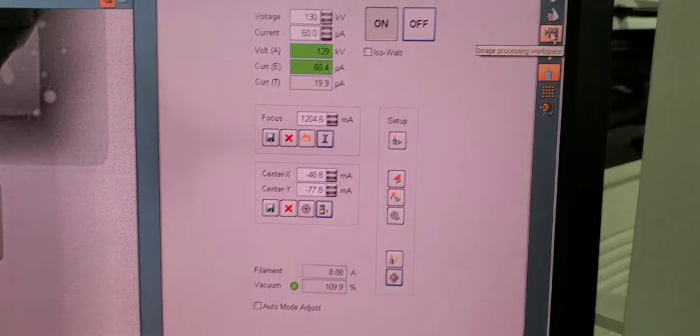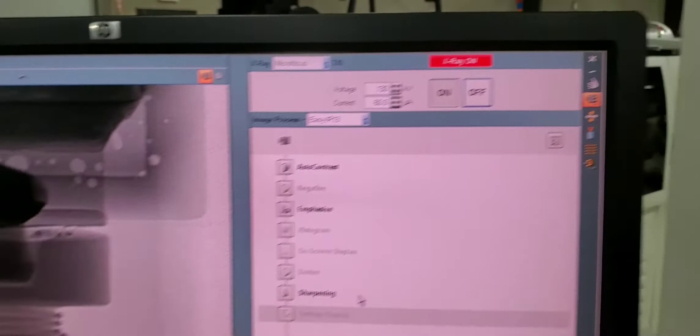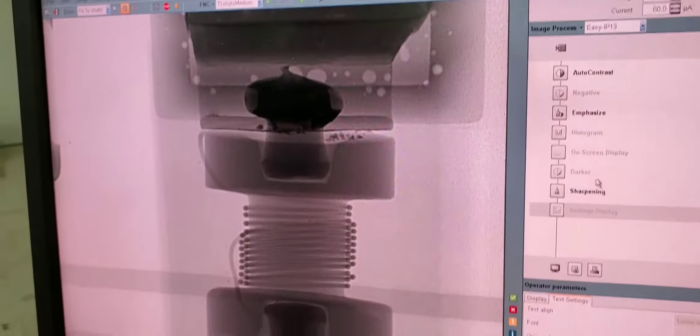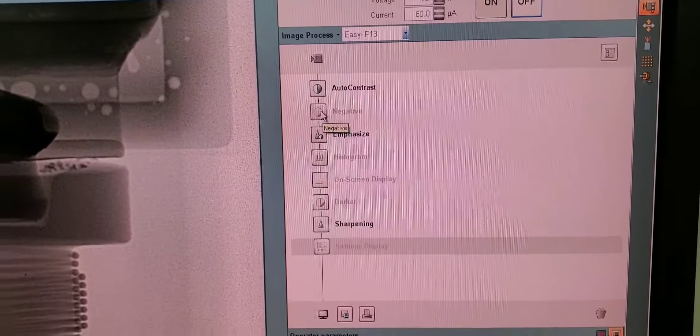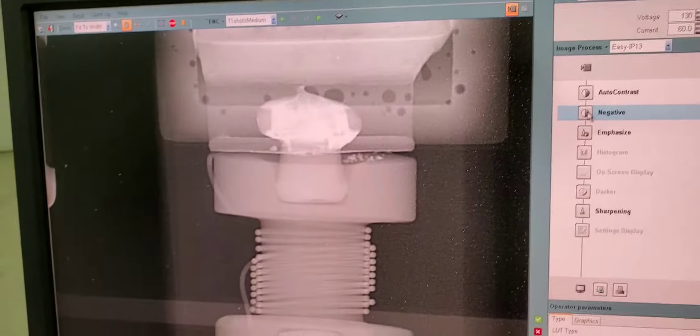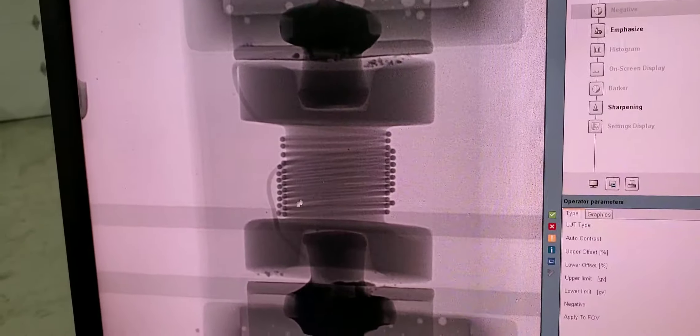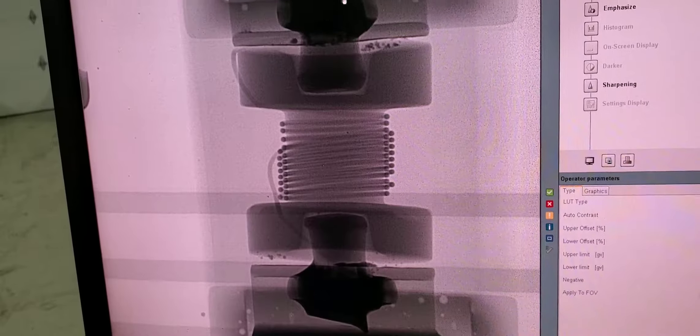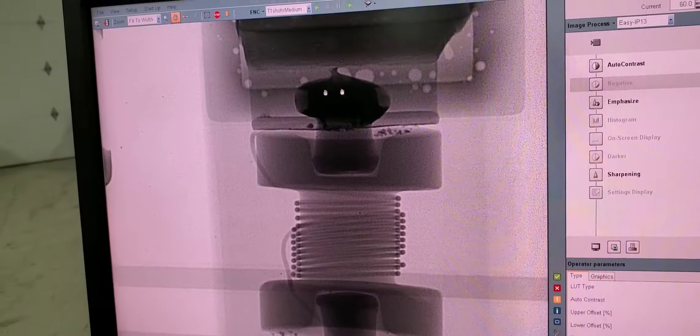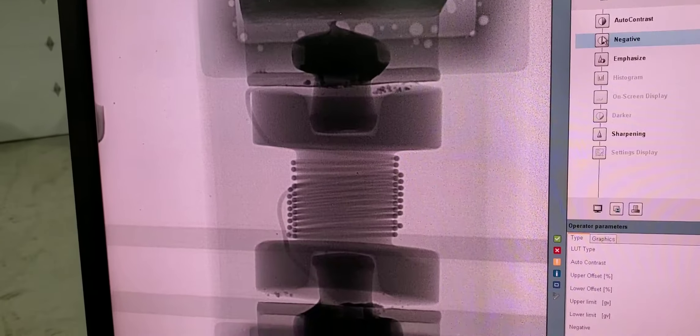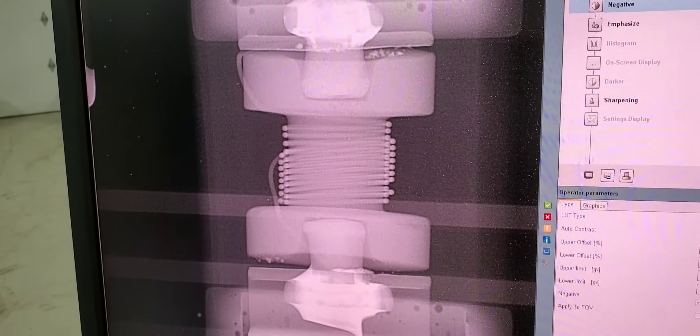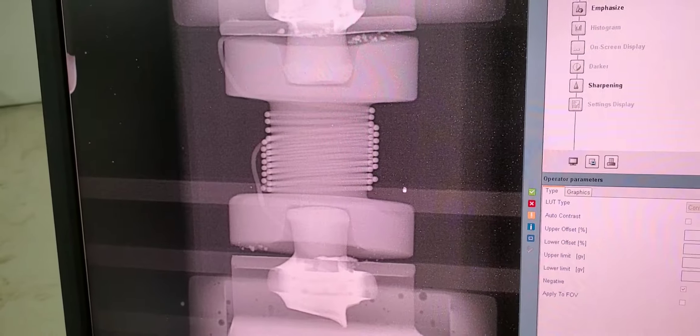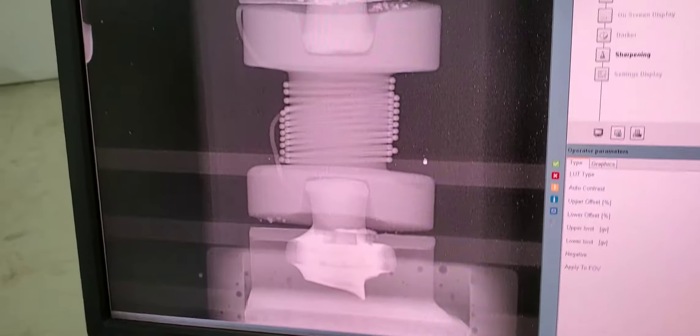Now we can switch to a different view. This is the view that will allow us to manipulate the image quality. We can turn on negative. So in this view, all the dark is the dense. Obviously, solder would be dark; that's why the voids show up light. If we turn on the negative, the voids will show up dark—just another tool to help inspect the component.